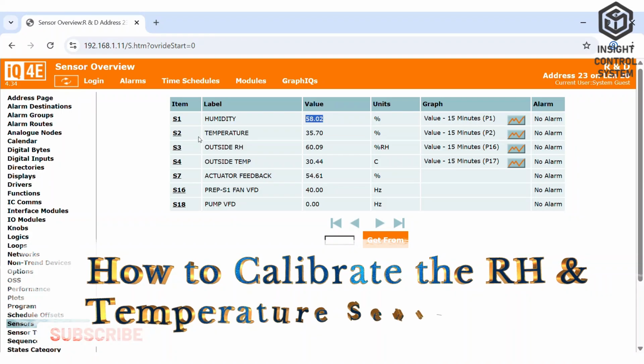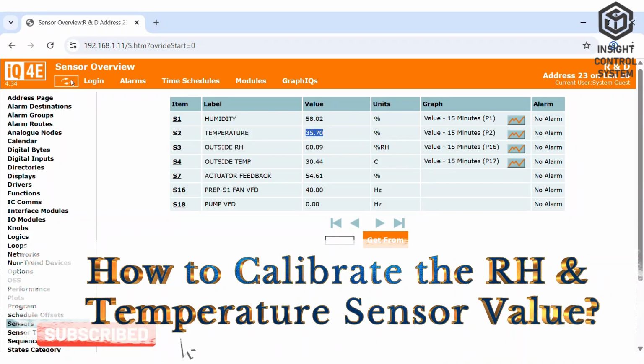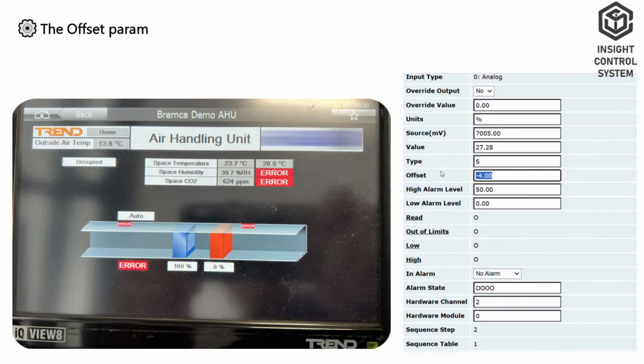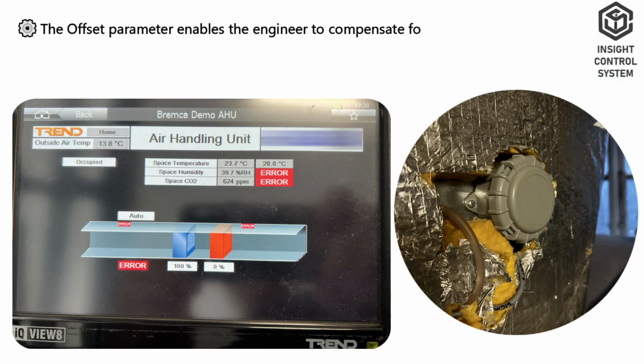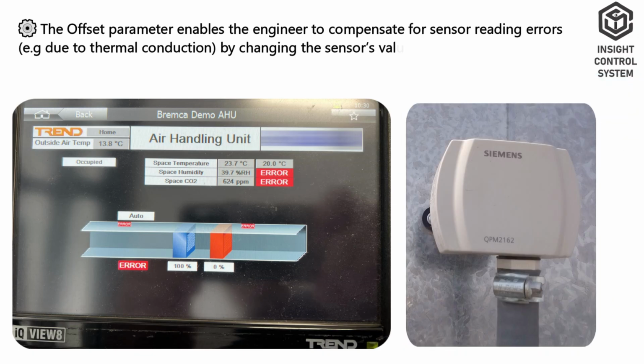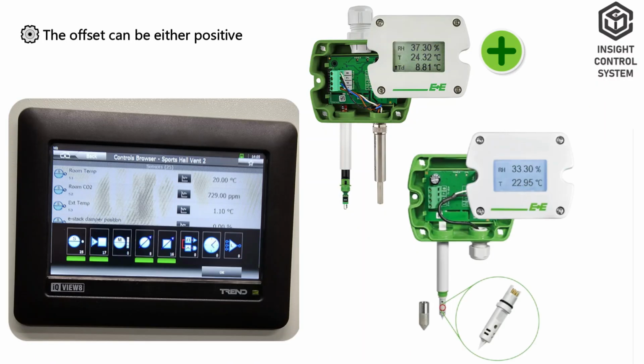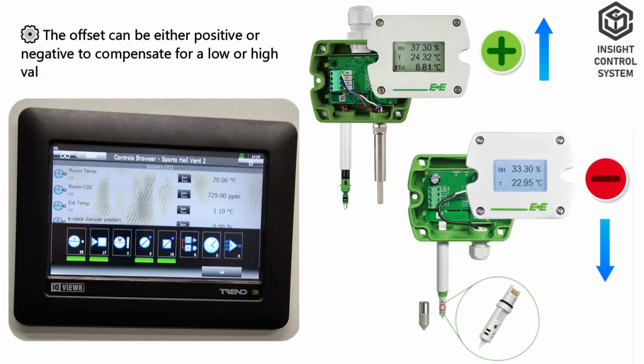How to calibrate the RH and temperature sensor value. The offset parameter enables the engineer to compensate for sensor reading errors, for example due to thermal conduction, by changing the sensor's value by a specified amount. The offset can be either positive or negative to compensate for a low or high value as required.